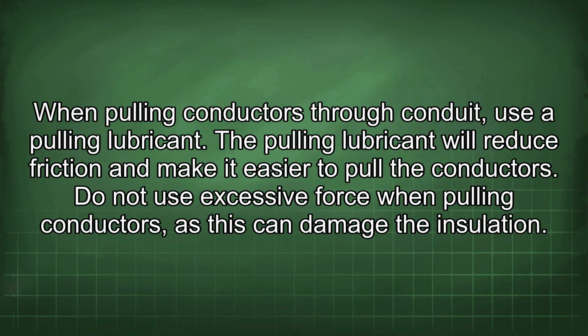When pulling conductors through conduit, use a pulling lubricant. The pulling lubricant will reduce friction and make it easier to pull the conductors. Do not use excessive force when pulling conductors, as this can damage the insulation.